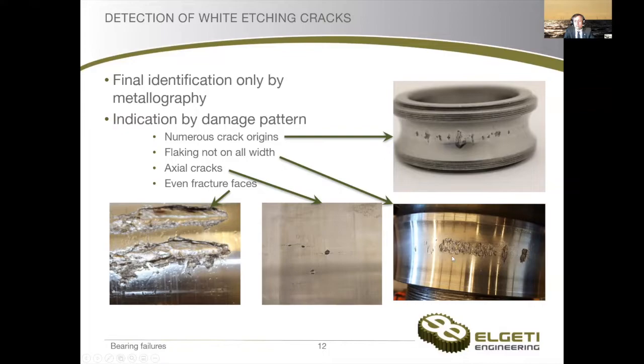Normally, in case of rolling contact fatigue, we have one, two, maybe three origins of flaking. If we have multiple of them, this means something is wrong with the material — it can be an excessive amount of inclusions or structural alteration, which mechanically have the same consequences. Then the next indicator would be flaking not on the complete width, like in this case. This is very characteristic — it means that somewhere here we have our white etching areas and here not. Axial cracks going along with pits is also something we will never see in pure rolling contact fatigue.